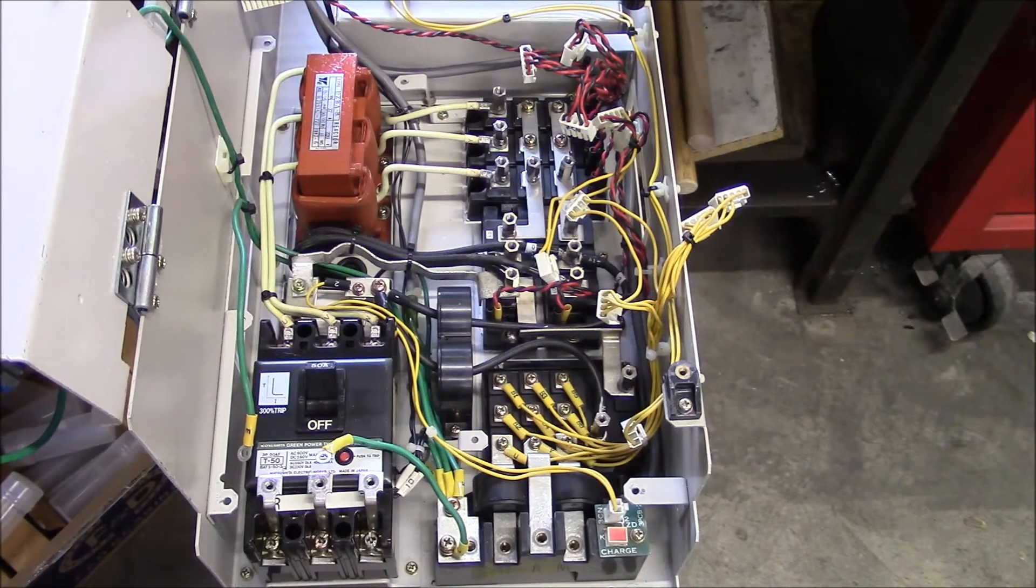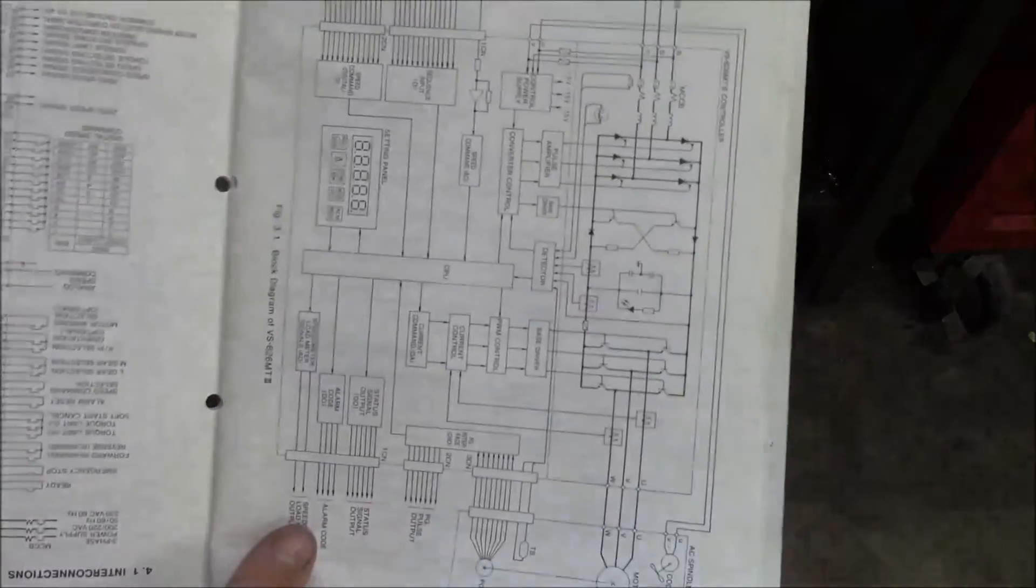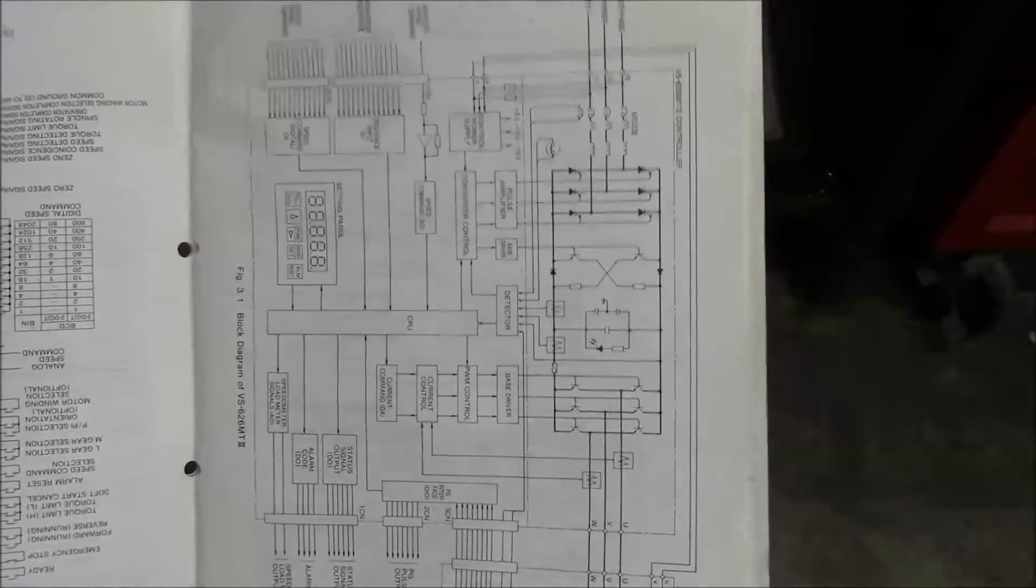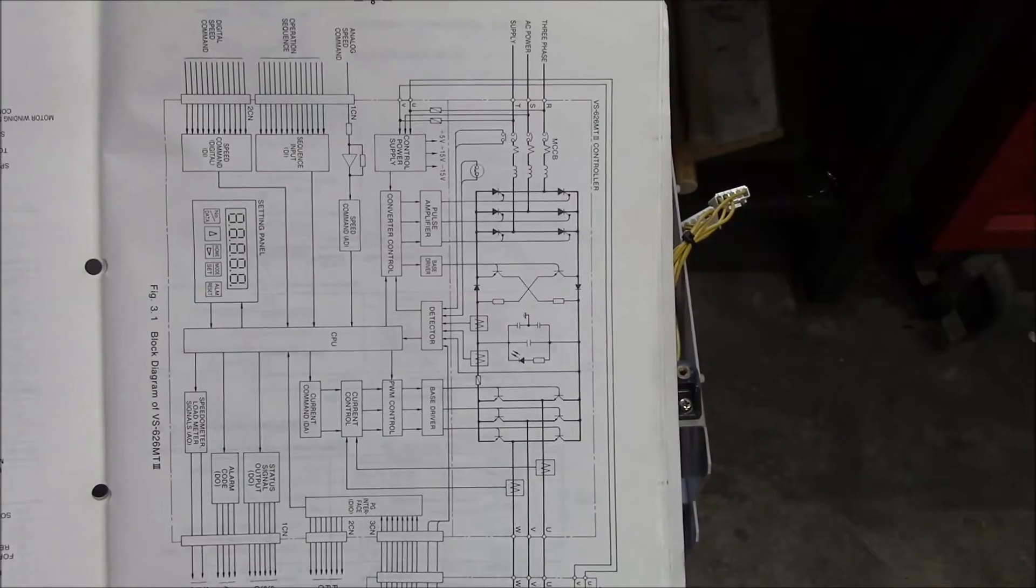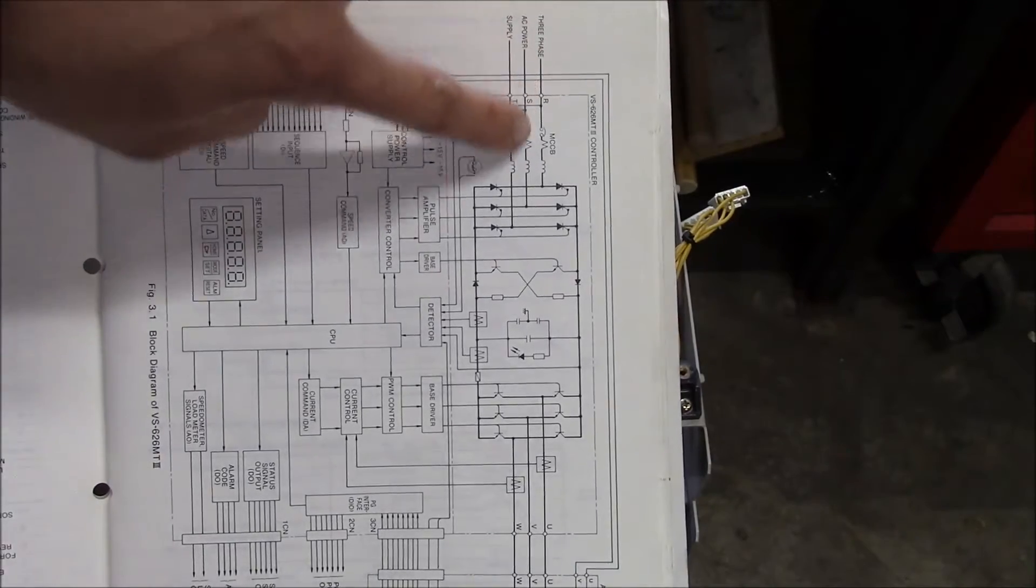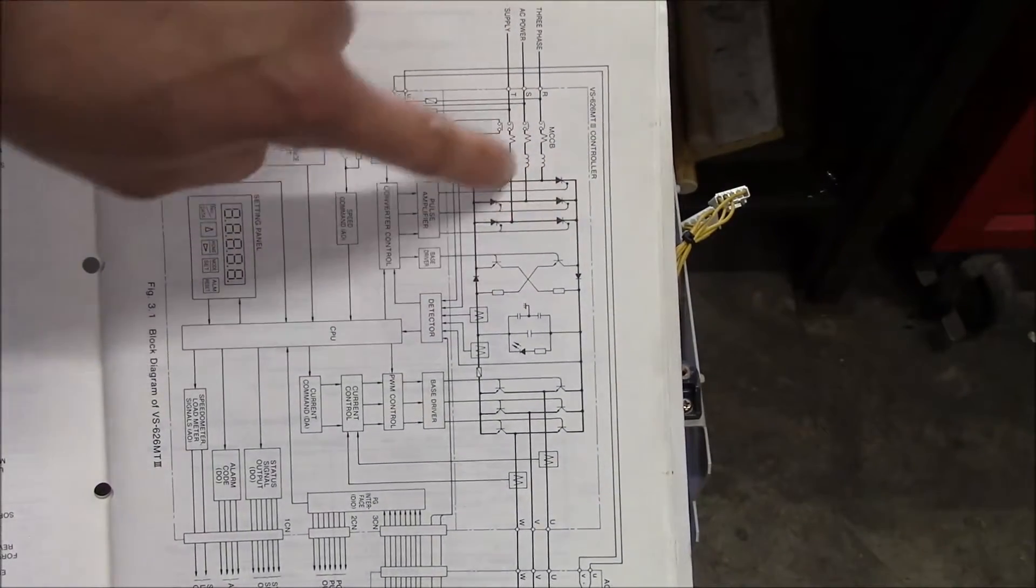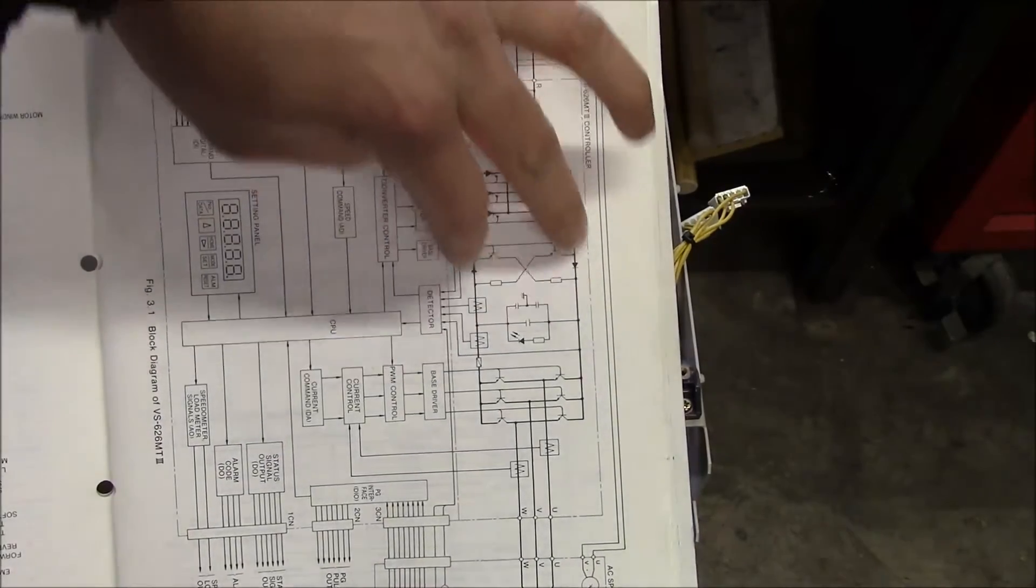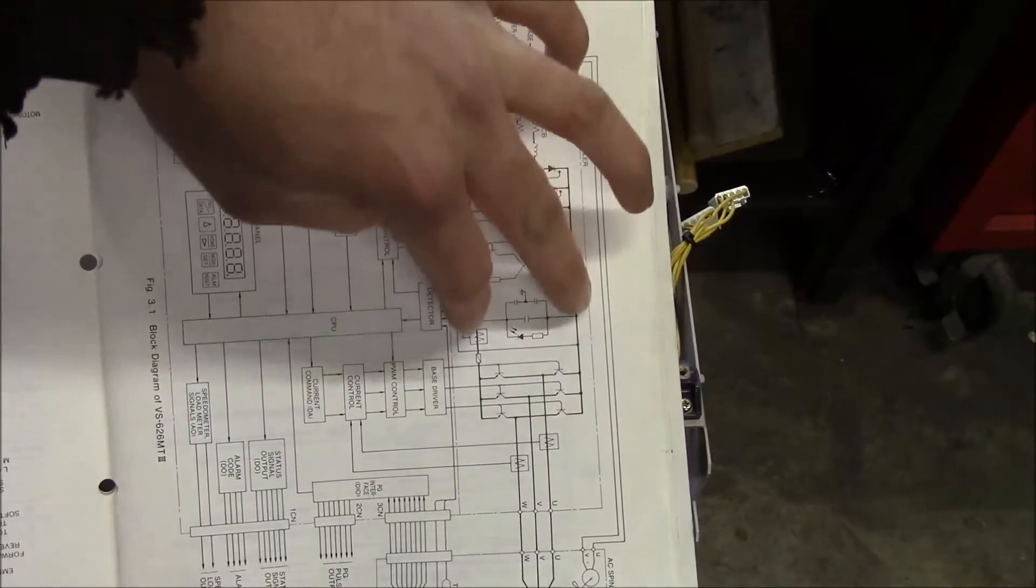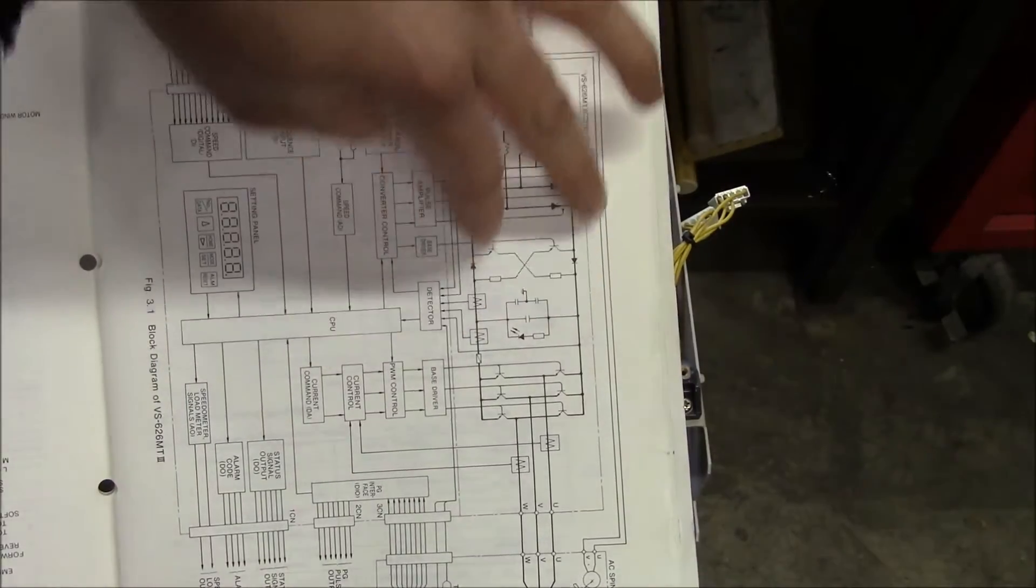So basically, I don't know if you'll be able to read this, but this is the schematic layout for this drive. So basically, three-phase power comes in, goes through a rectifier here, goes into this set of contacts here. That's the DC bus.